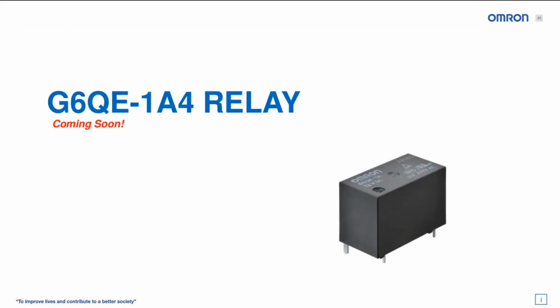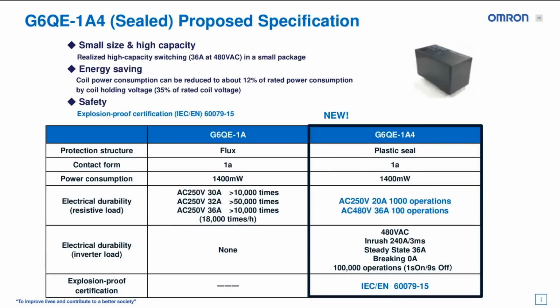And the last upcoming product that is confirmed is the G6QE1A4. And that 4 here is indicating a sealed type product. So this is sealing of an existing product, just like we did for the G5PZ, offering different ratings, but offering that explosion proof capability. So 36 amp at 480 VAC in a very small package is what this product has to offer. It has energy savings in that you can apply a holding voltage to the coil. So once you empower that coil with the full rated coil voltage, you can drop that back to 35% of the rating and still keep the contacts engaged, greatly reducing the power consumption of the relay while it is activated.